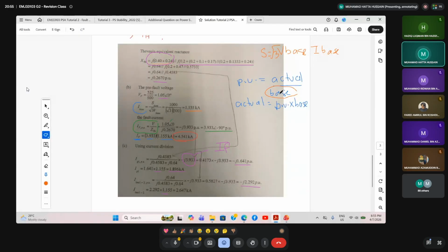But remember, since we already determined the pre-fault voltage as 1.05, we have to use Ohm's law: IF per unit equals V divided by Z Thevenin, or X Thevenin. So V equals 1.05 at 0 degrees, the pre-fault voltage, divided by the value of X Thevenin or Z Thevenin.